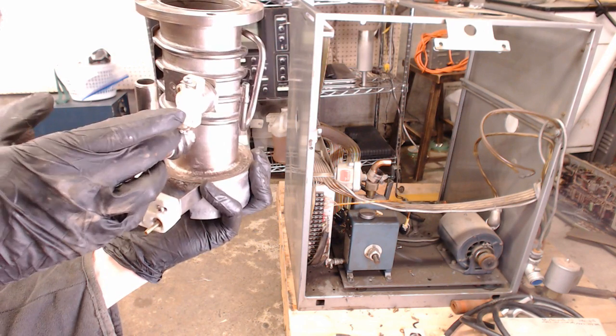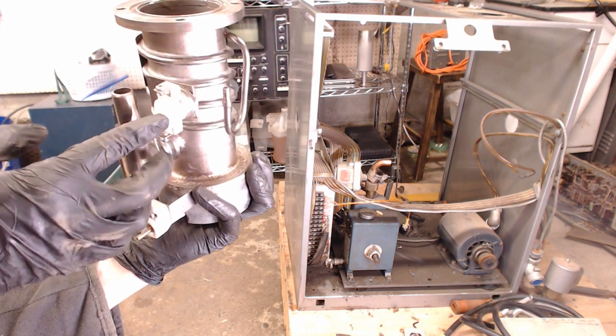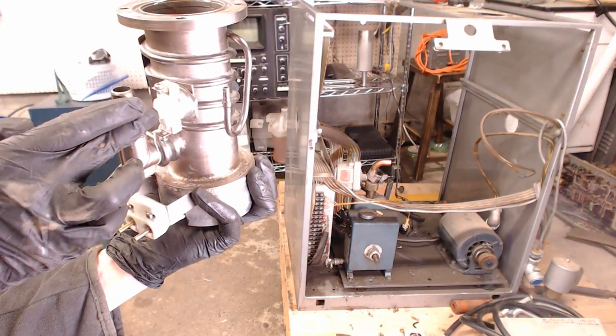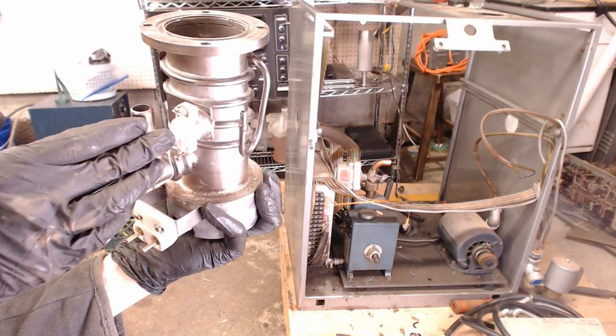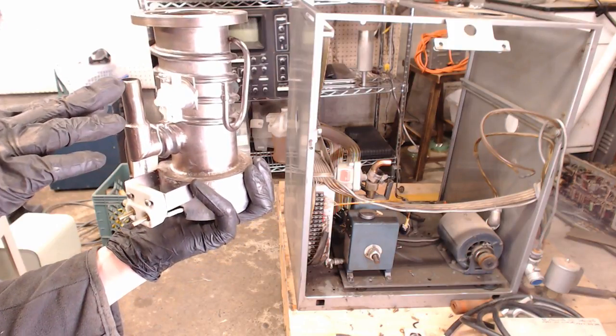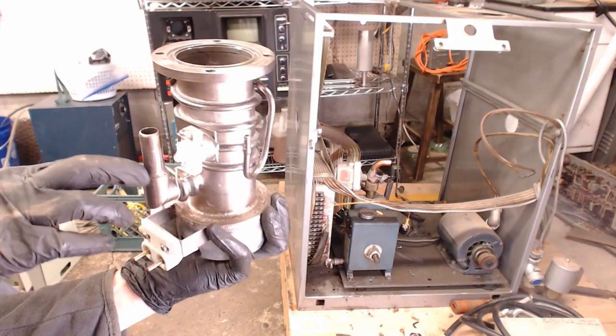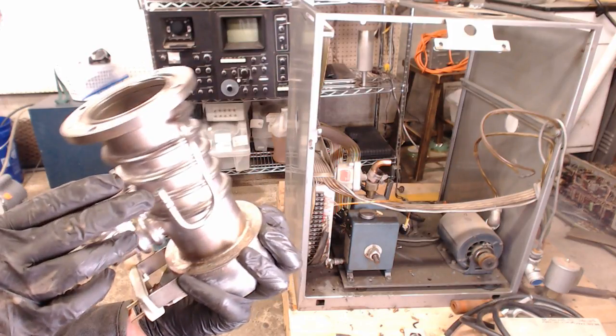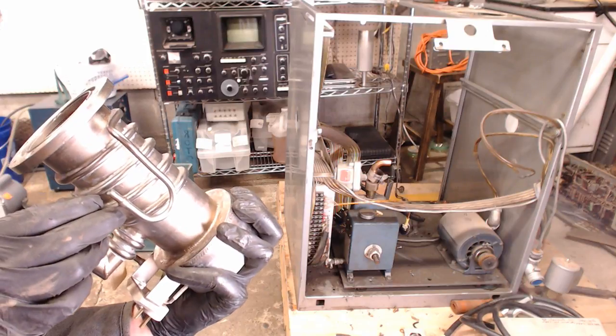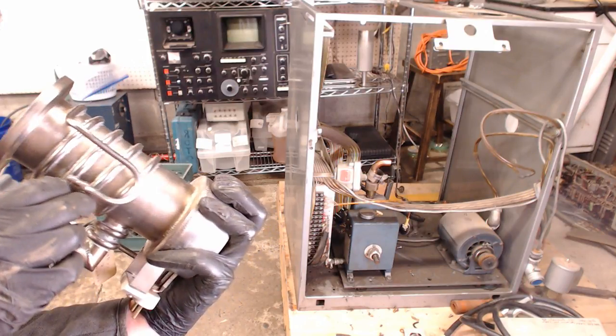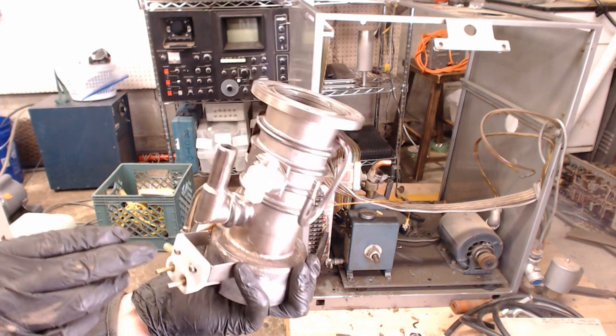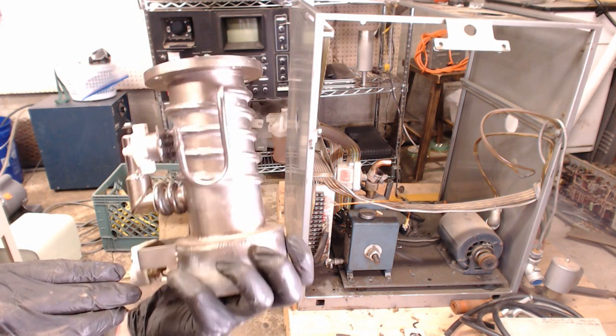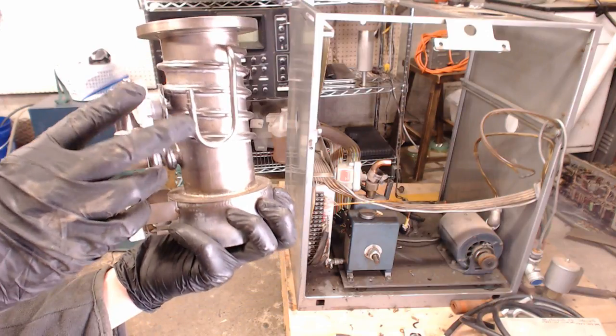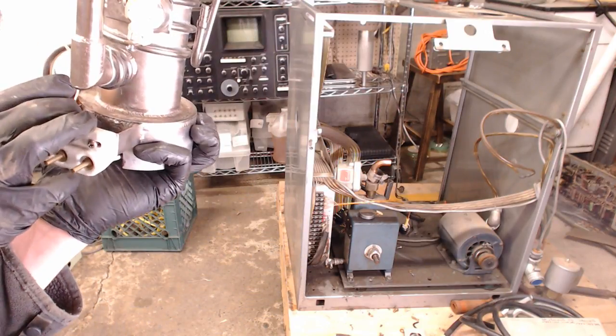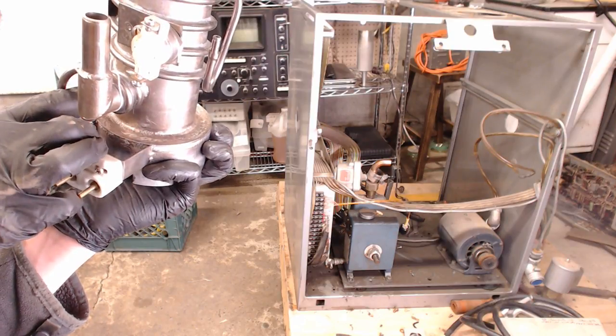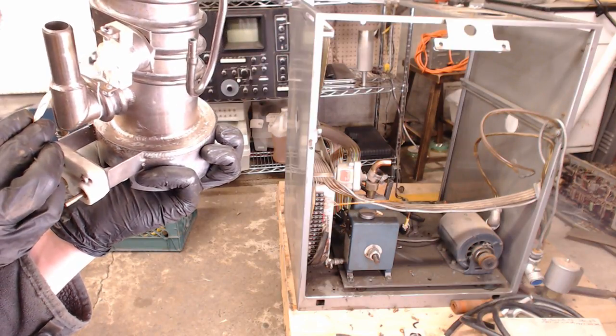This is a thermal cutoff switch. So it just shuts off if the water supply turns off. This button pops out, or is kind of forced out, and just turns the diffusion pump off, and that way you don't dump a bunch of heat where there shouldn't be a bunch of heat in the microscope. Because that's bad for things, it turns out. O-rings that aren't designed to get hot don't like getting hot very much. So that's the diffusion pump. And the other one, instead of being water cooled, is air cooled, so those baffles on it were for that. But you can't take apart the other one nearly as easily as you can take apart this one.